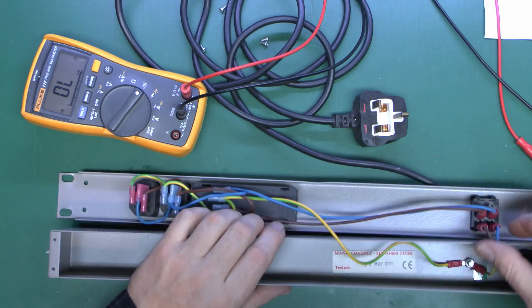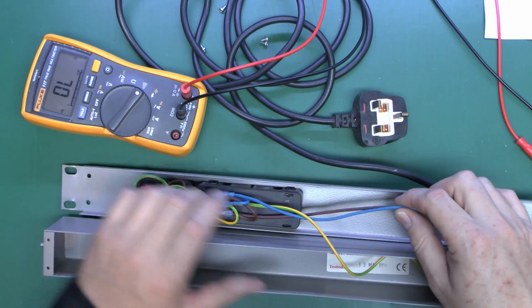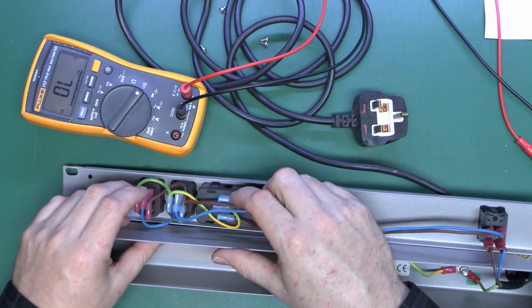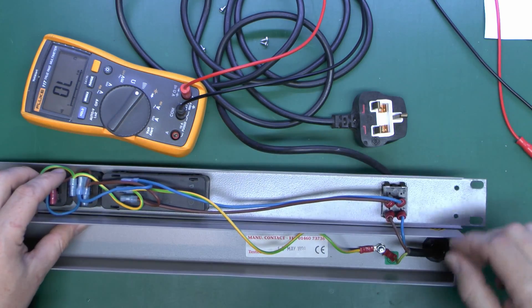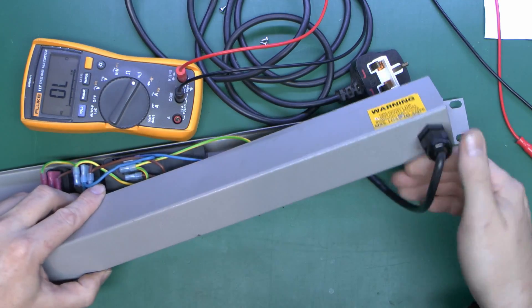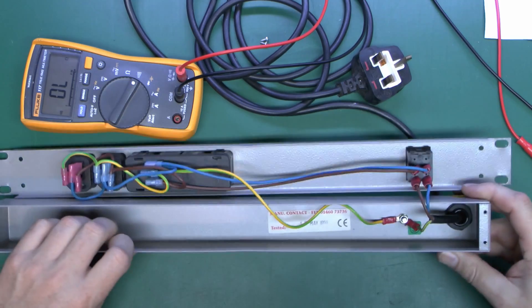Now, it's a bit of a mystery why this would trip the circuit breaker, because there's not really a lot in here. It's just the outlets here, which are all wired with these insulated connectors. And again, the same with the switch there. And the cable does come through this sort of plastic strain relief arrangement. So again, that's perfectly fine.